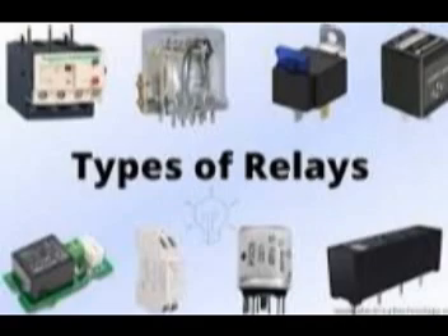For short delays, like a fraction of a second up to maybe a few seconds, you can use a copper disc or slug fitted near the coil and armature. When the coil de-energizes, the collapsing field induces eddy currents in this copper. These currents create their own temporary magnetic field that opposes the change, slowing down the release of the armature. Like a magnetic brake. Kind of, yeah.